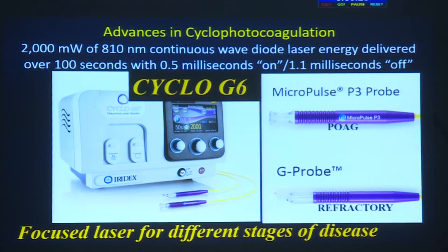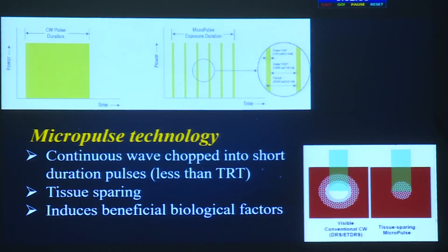In India, the CycloG6 is now available, using an 810 nm continuous-wave diode laser. The Micropulse P3 probe and G probe are available for refractory glaucoma; the P3 probe is used for primary open-angle glaucoma patients. 2,000 milliwatts of diode laser energy is delivered over 100 seconds within 0.5 ms on and 1.1 ms off, delivering a 31.1% duty cycle — essentially a continuous wave chopped into short pulse durations less than the thermal relaxation time.